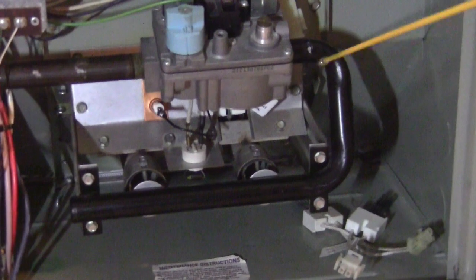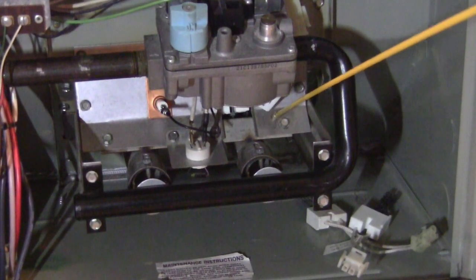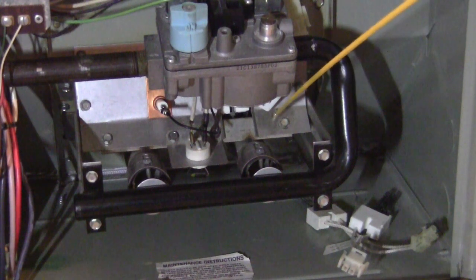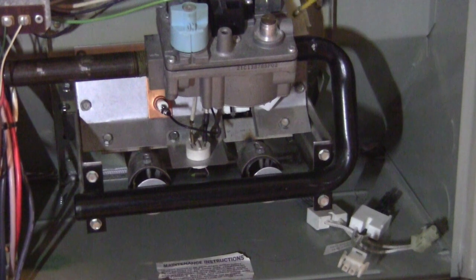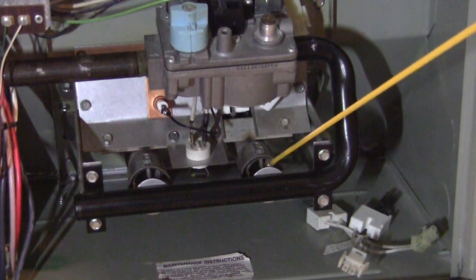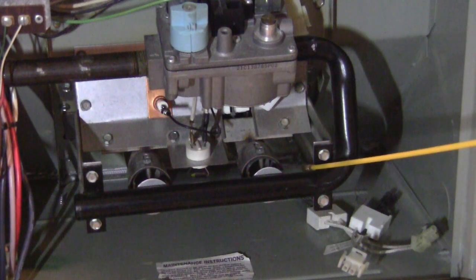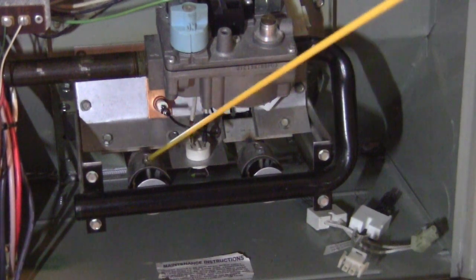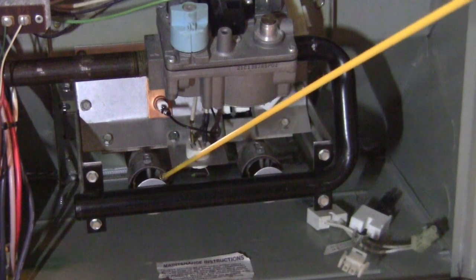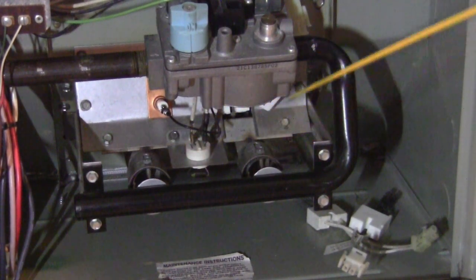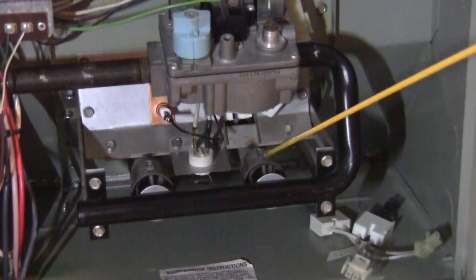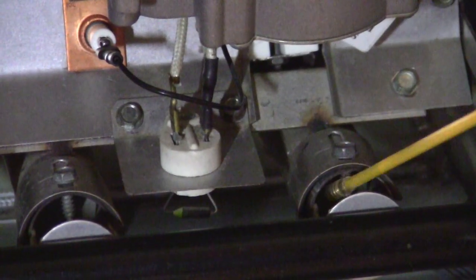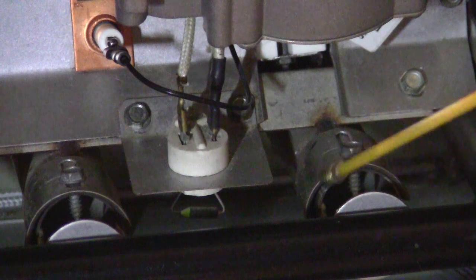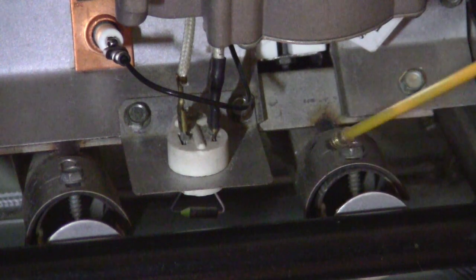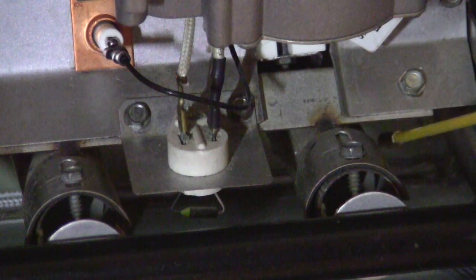So if the igniter down here is burning red hot, after about 4 or 5 seconds the controller will release the natural gas from here into here. Because the fan is building up a vacuum inside the chamber, these two pipes suck up the gas from here. If you don't have the vacuum, the gas will leak from here to the outside. But because of the vacuum, and the burner actually has a gap over here, totally open here, the gas gets sucked up into here and then it can burn inside, because the igniter is over here.